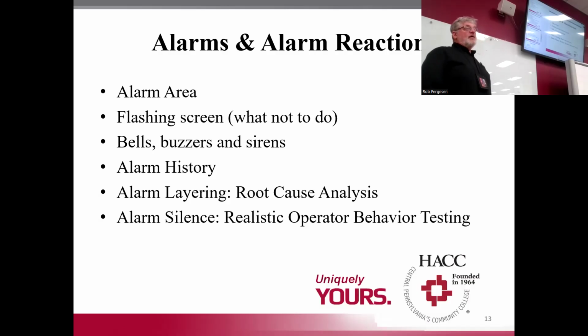We generally don't want an audible alarm or a flashing alarm to keep annoying operators, because they'll find creative ways to cut them off, i.e., look at that wire. Now you've cut off the alarm. So you don't want that to occur at all. You have to create an alarm silence that's common sense, and you also have to make sure you don't lose track of alarms and that they continue to raise attention to areas that might be causing a problem. In some cases, you might find out the alarm that you're raising isn't real, and maybe you should take it out of the system.